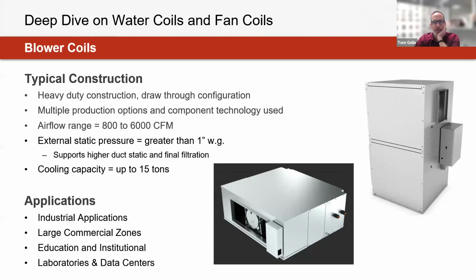DOAS fan coil unit, you don't really need a DOAS. If you have just a heat exchanger to pre-treat your outside air, you're going to be 45 degrees in the wintertime, and you'll be down to 80 in the summertime. That fan coil can handle it. So dump the DOAS. You can just put a wheel system with freeze protection if you need it, and then go right to these fan coils, and you've got yourself a system.